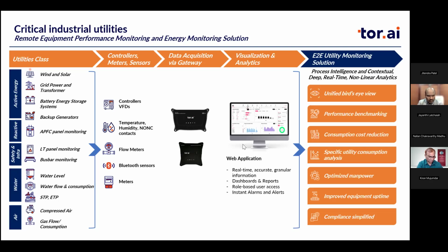Next is the busbar temperature monitoring. The busbar is the one which carries the power from source to the load. Generally, high-rise buildings, heavy industries, or systems that carry heavy current or run heavy motors are generally run by bus bars. There will be joints in the bus bar of different shapes and sizes, and also a joint from the bus bar to the cable. Generally, the rise in temperature happens at the bus bar joints.